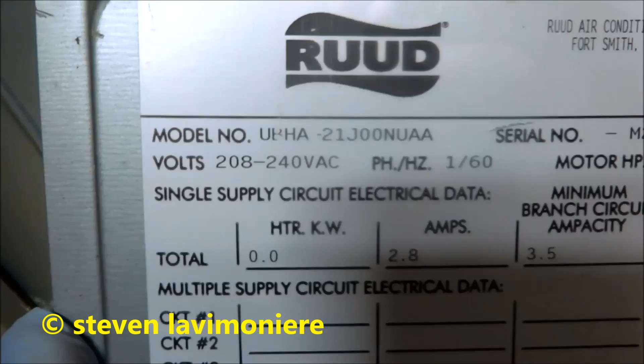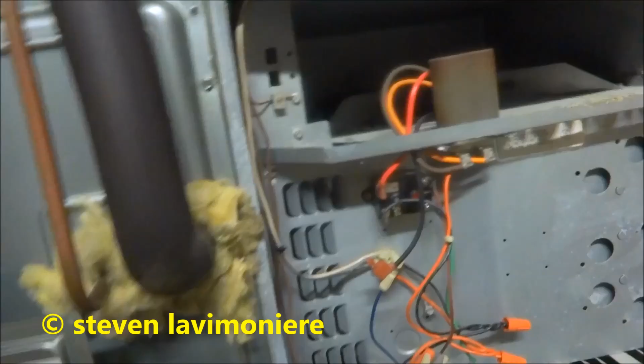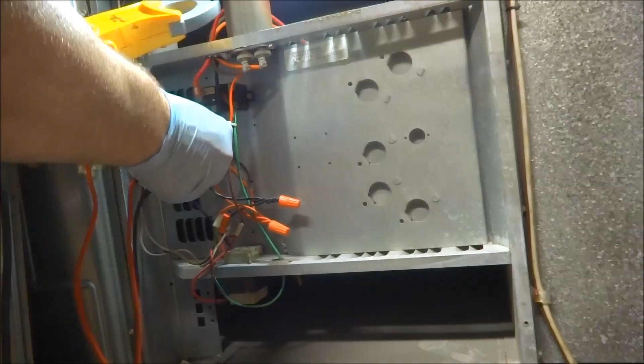Alright guys, I got the cover off. We're going to check the unit here. This power's on. I'll check if we got power. It might be this relay's bad. We'll check it. Motor's not hot. So we'll check voltage, see if we got voltage coming in. 240. Oh, we got voltage there.